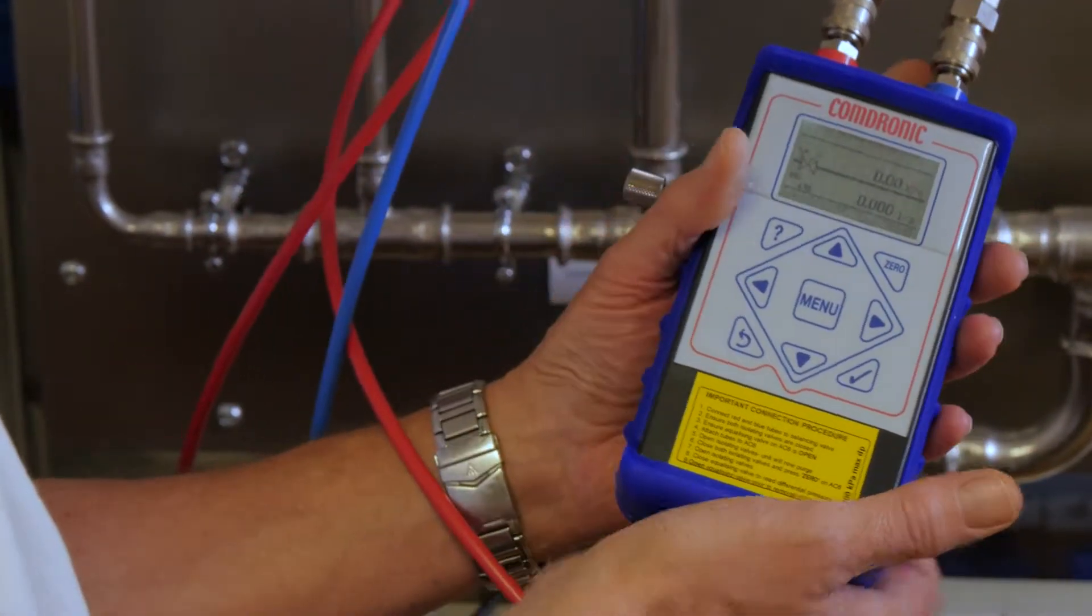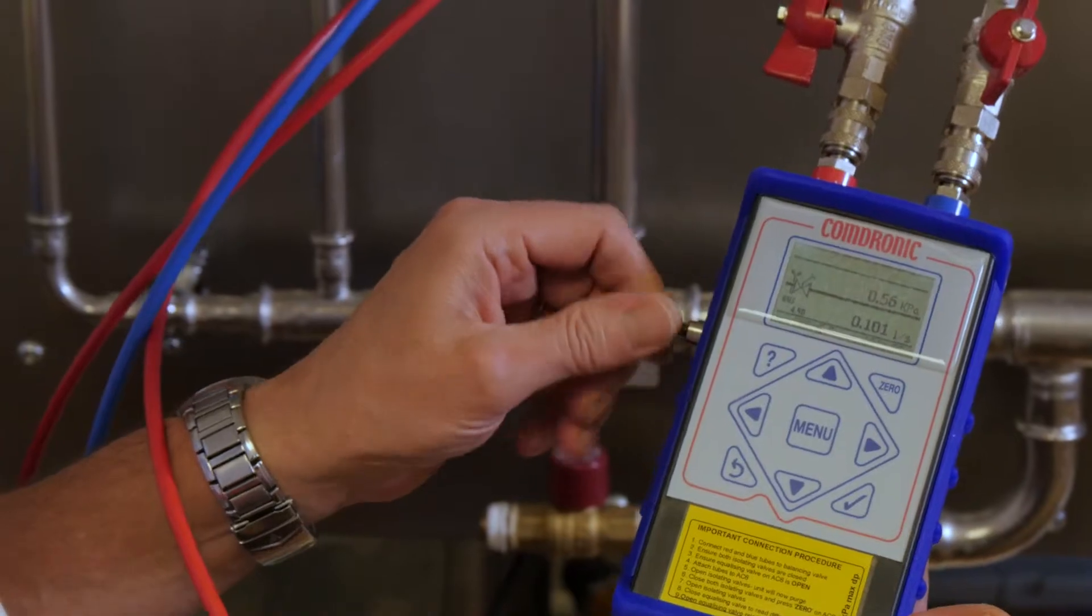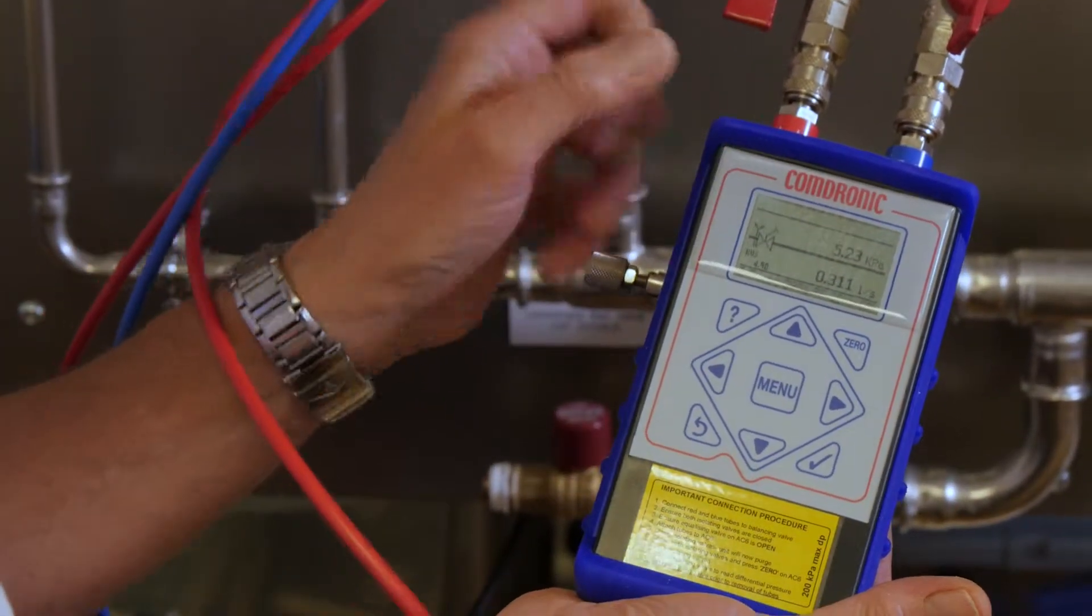We've zeroed it. Open the valves again. And then we close the equalizing valve on the side of the unit. And as we close it we'll see the differential pressure is rising.